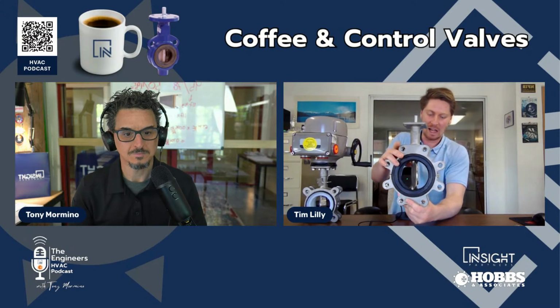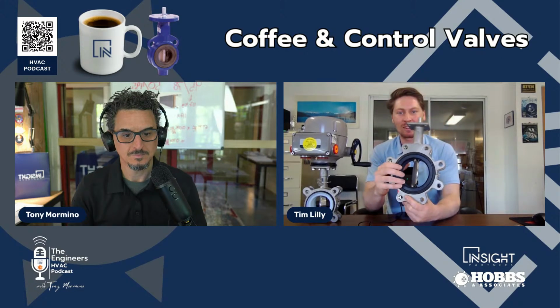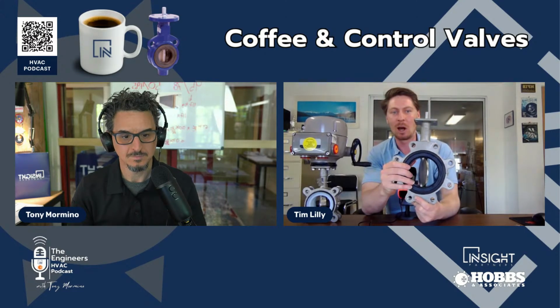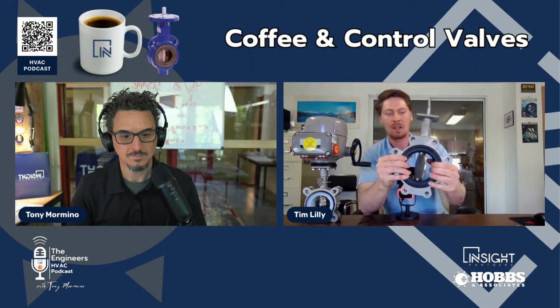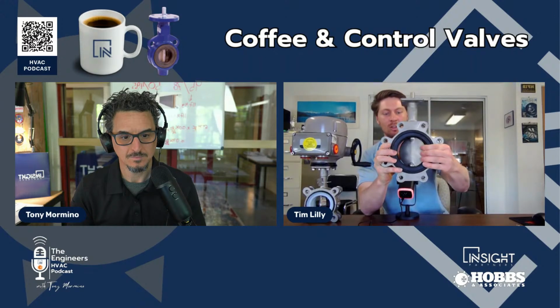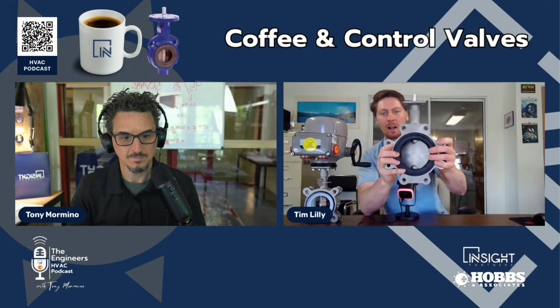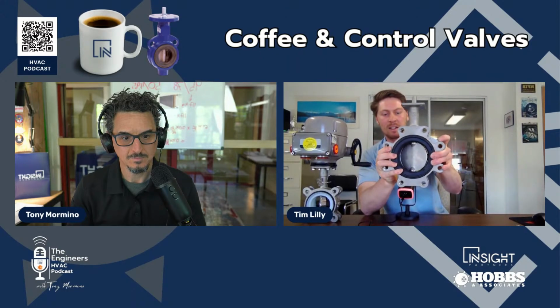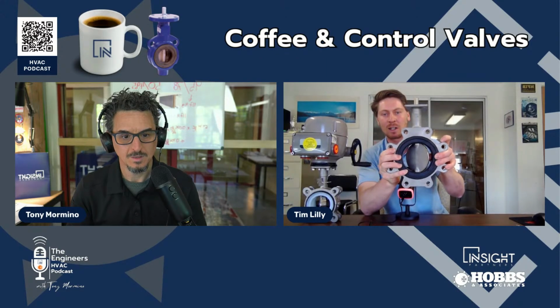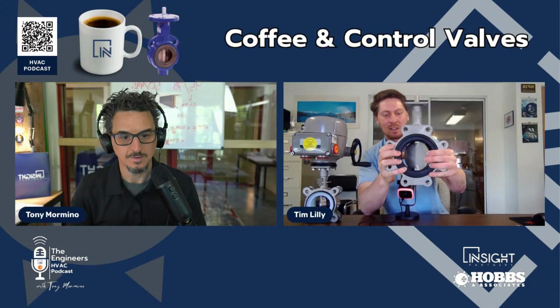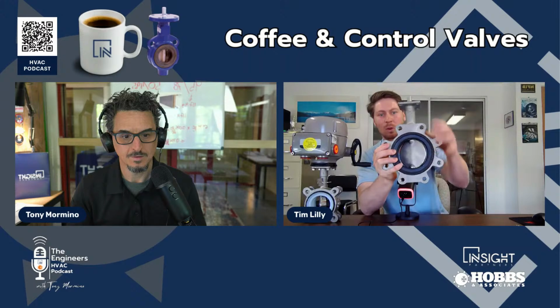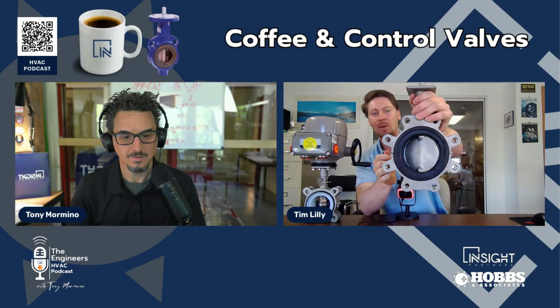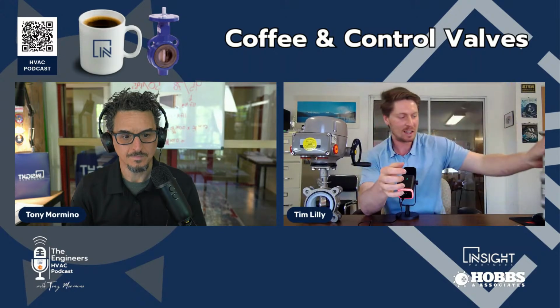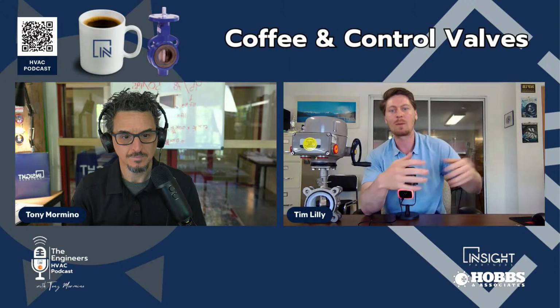I know some people listening to this podcast probably install a lot of butterfly valves. The number one reason a butterfly valve fails is that when you install it in the closed position between your two flanges, you clamp down on it, and the first time it comes out of the seat, you rip your liner, and it starts leaking before you even run water through it. If you can install your butterfly valve at about 3% open, just enough to be outside of that liner, you'll extend the life of the valve tremendously.